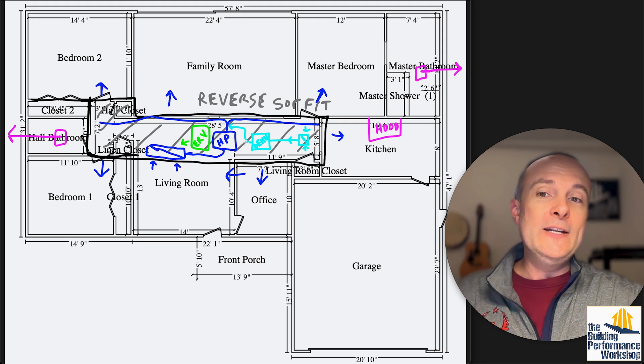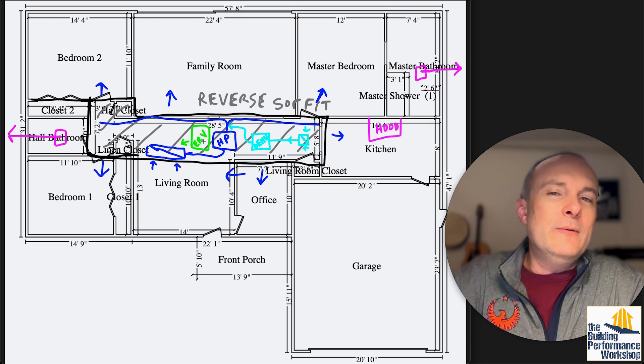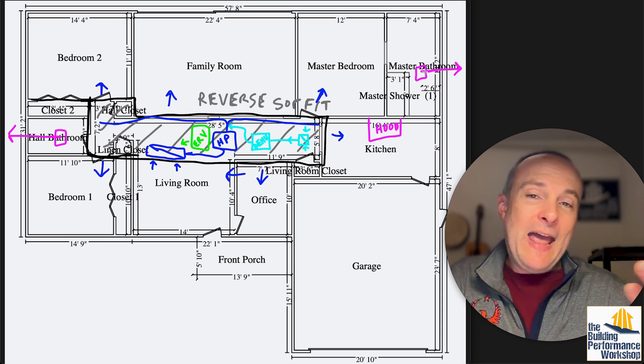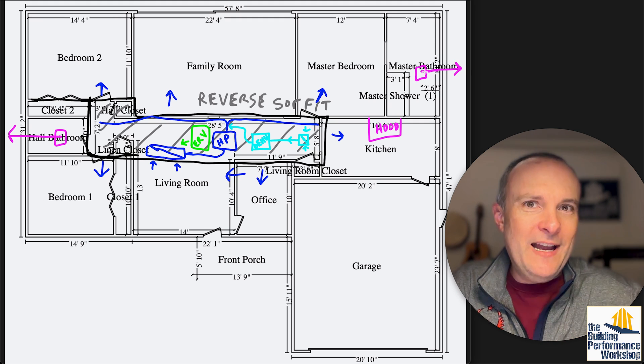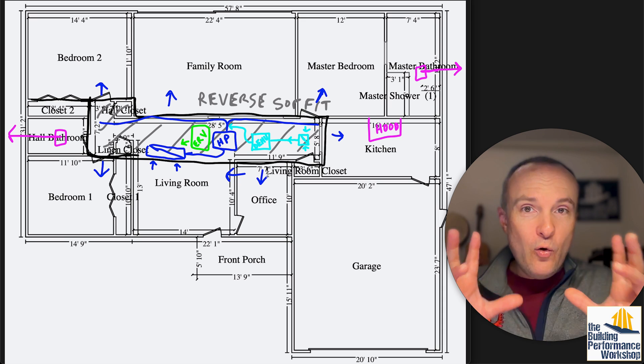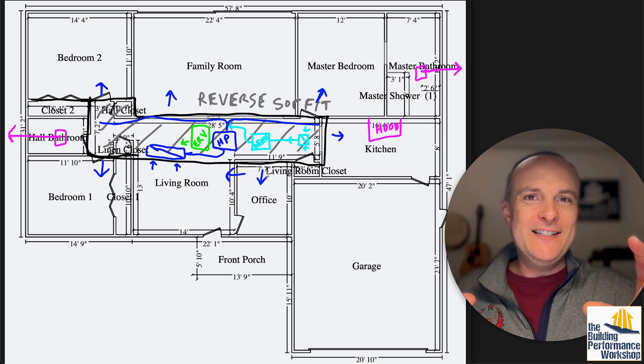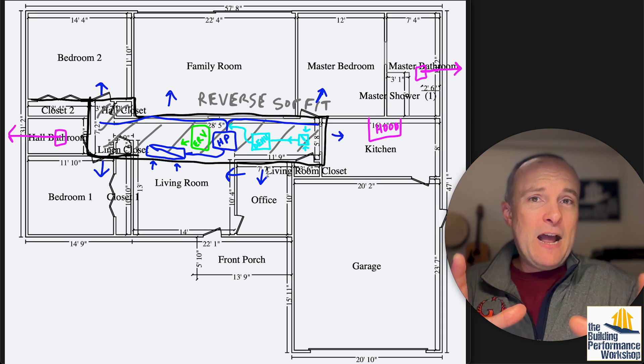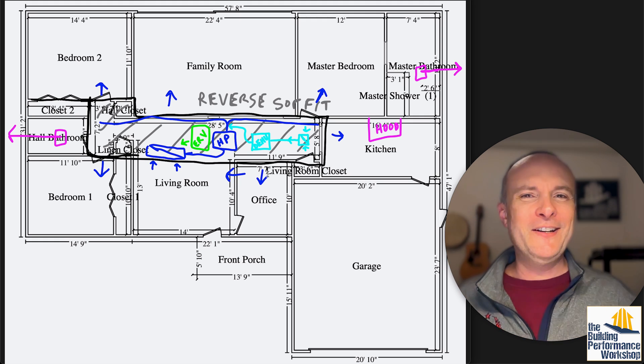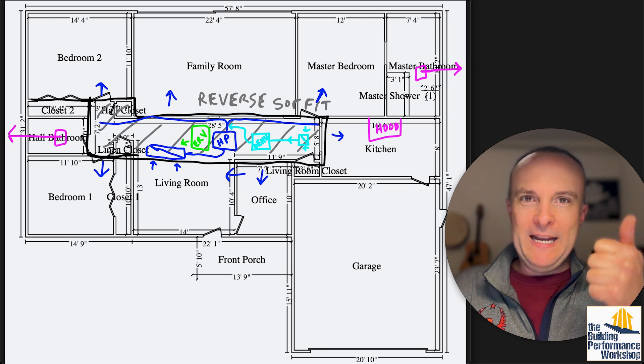We've got the ability to distribute dilution air coming in, taking stale air from the central hallway. We have filtration built in with the filter here, or inside the ceiling plenum — you want to make it easy to access. We have the distribution of dehumidified air, which in Florida is super, super important, especially when using an ERV. This kind of system could solve all of his problems. The whole crux of this design is that his floor plan is so beautiful for this. When you go to visit a home and you're thinking of buying it, think about how easy it would be to do something like this. If it's got big wide open spaces and vaulted ceilings, no way — you're looking for a very specific geometry when trying to do this approach.